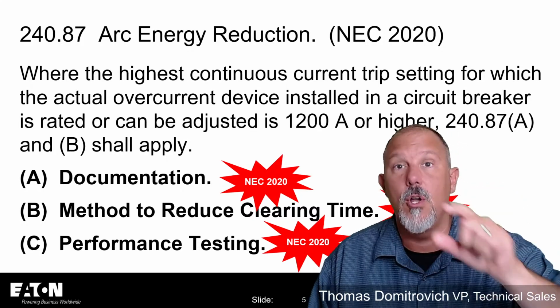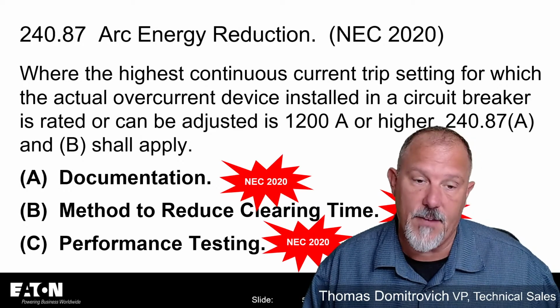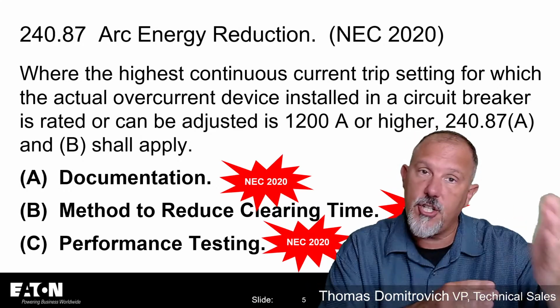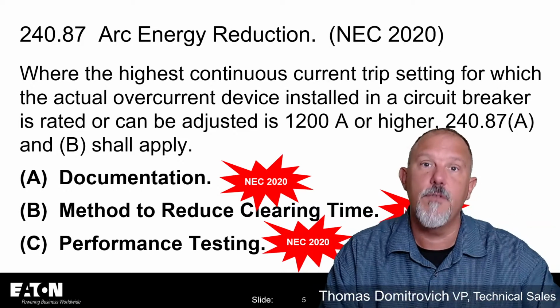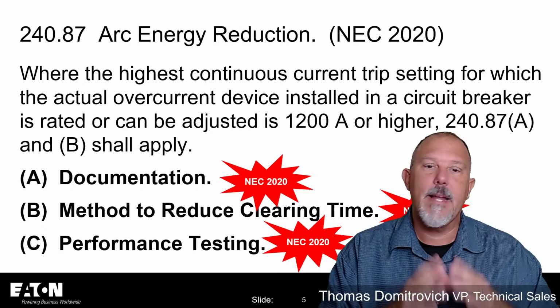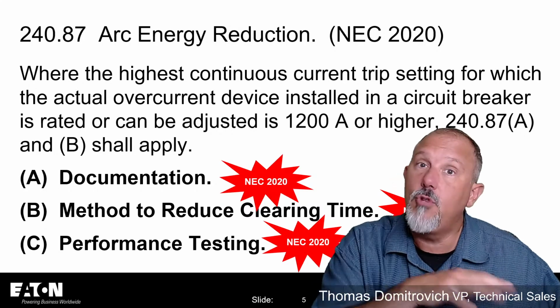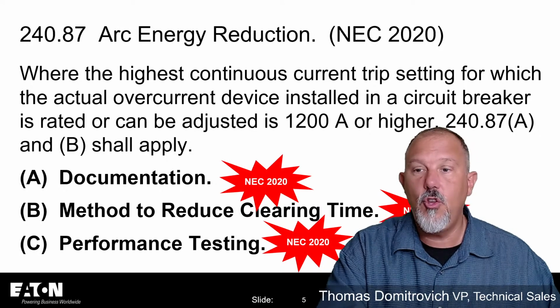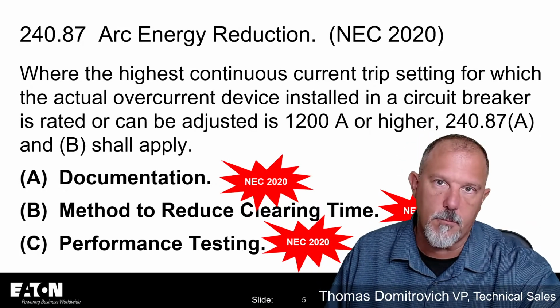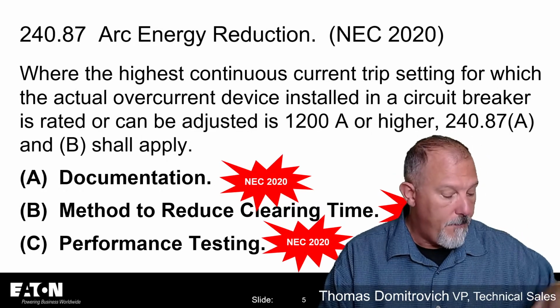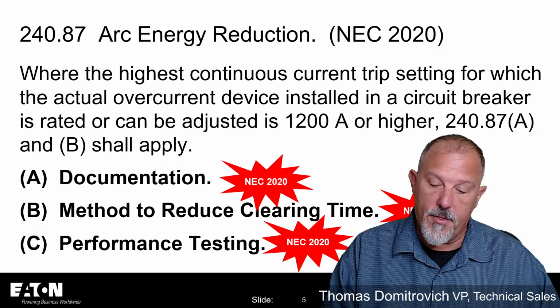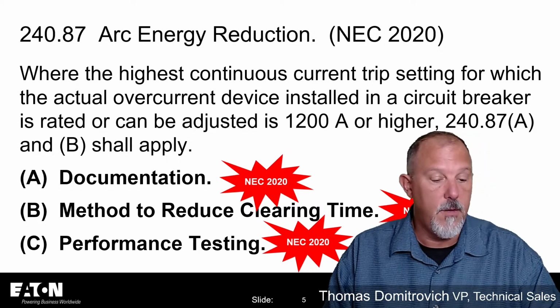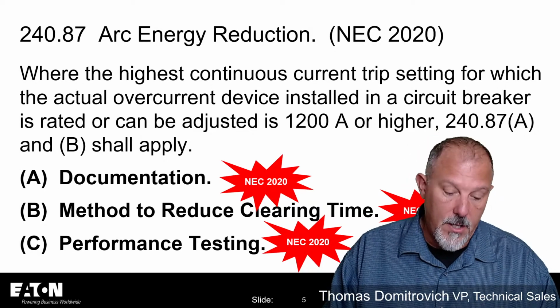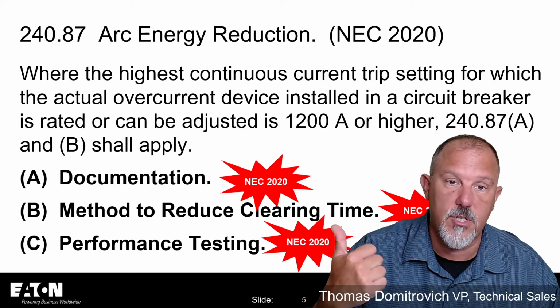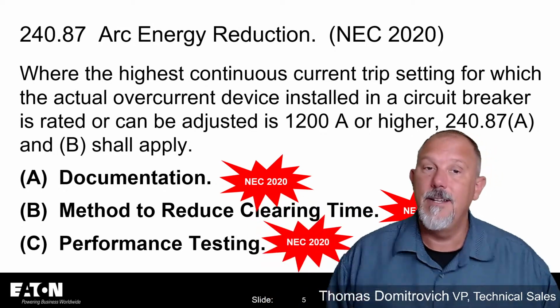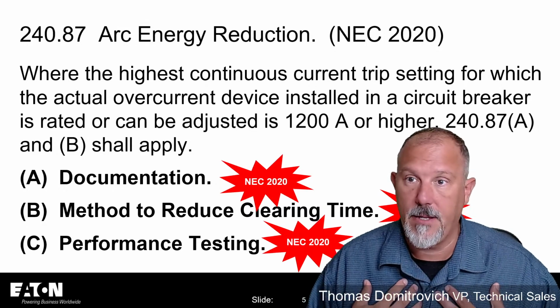So it's easy to recognize when you are into 240.87. To your first question, should you catch it in plan review or look at it in the field? Plan review is your first place. Plan review is critical, in my opinion, because if you don't catch it in plan review and wait to go out in the field, you see a 1200 amp circuit breaker, and now you have to get into whether or not it has, what are the technologies, right? In 240.87, when I get to the method to reduce clearing time and the documentation, you're too late, in my opinion.